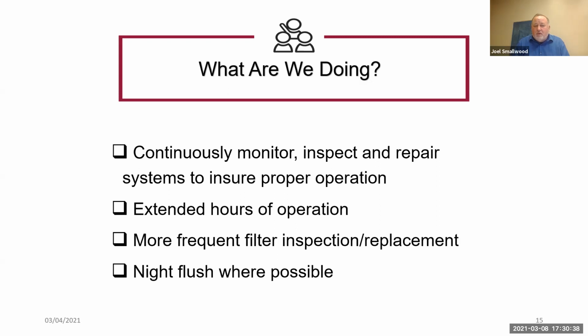And then what we call a night flush, and I say where possible. Many of our systems are capable of doing this, not all of them, but it's really just what it sounds like. The ventilation system turns on, it's pulling in outside air, it doesn't heat it or do anything to it, it just brings in outside air and exhausts air. The problem is we have to be really cautious with that, because once again, it will damage our systems if it freezes them up.